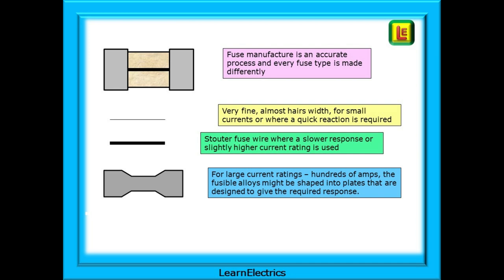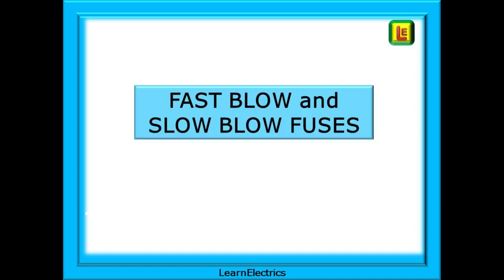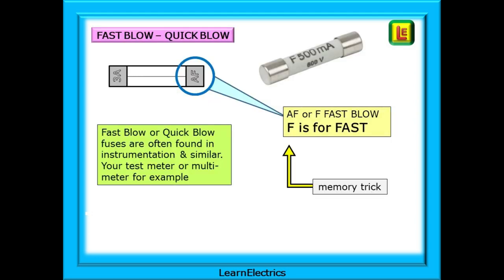Making fuses is an accurate process and every fuse type is made differently — from very fine, almost hair's-width wires for small currents or where a quicker reaction is required, to a much stouter fuse wire where a slower response or higher current rating is needed. For large industrial machinery applications where hundreds of amps are common, the fusible alloys might be a shaped plate designed to give the required response to overloads. You may come across fast blow and slow blow fuses. A fast blow or quick blow fuse does just what it says — as soon as the current exceeds the rated value, it blows instantly. These are generally found in instrumentation panels or in your test meter, protecting delicate parts of the printed circuit board. To remember: F or AF on the fuse means fast blow — F is for fast.